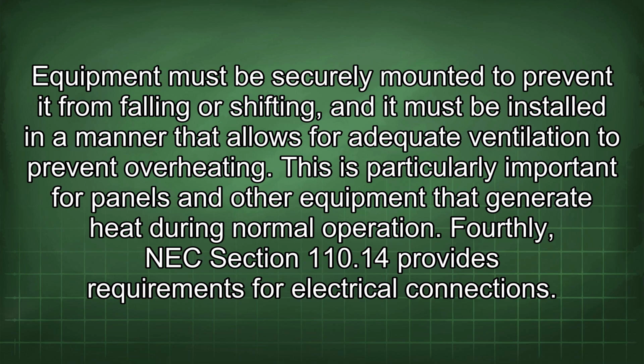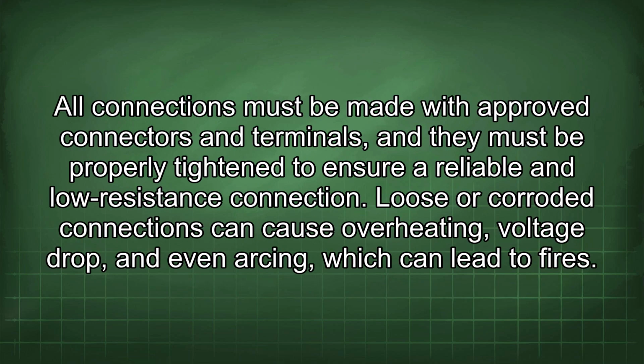Fourthly, NEC Section 110.14 provides requirements for electrical connections. All connections must be made with approved connectors and terminals, and they must be properly tightened to ensure a reliable and low-resistance connection. Loose or corroded connections can cause overheating, voltage drop, and even arcing, which can lead to fires.